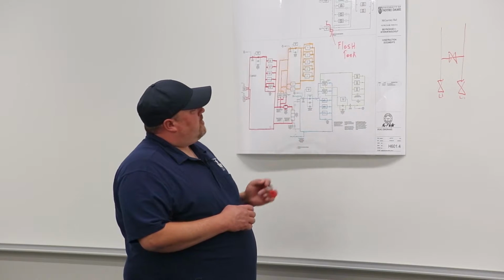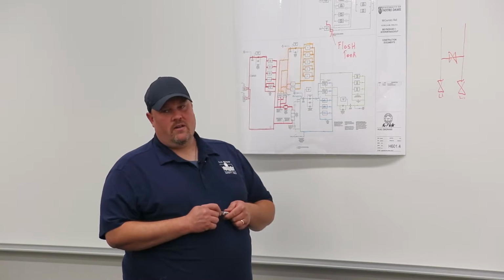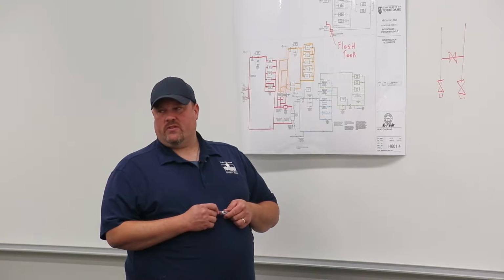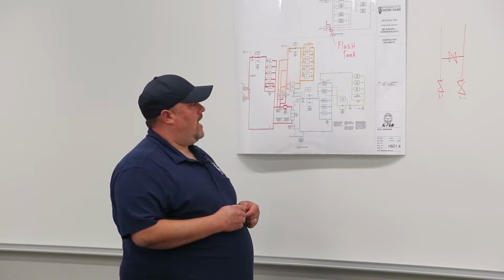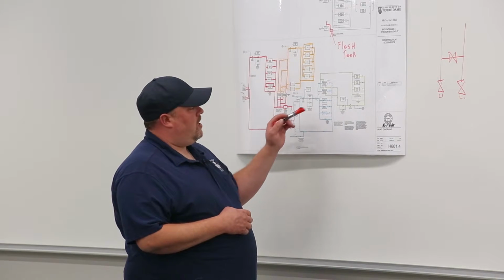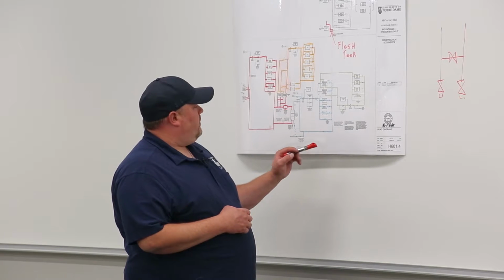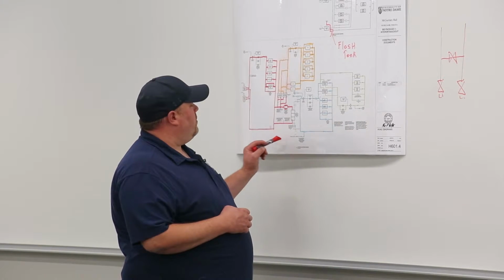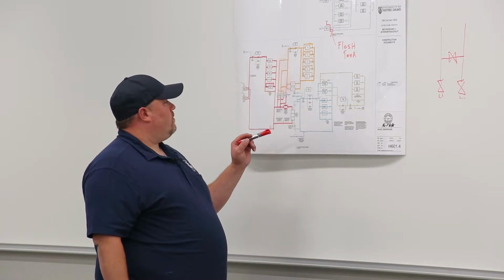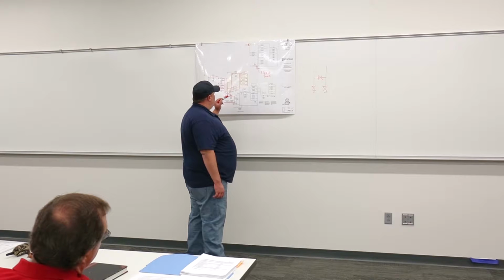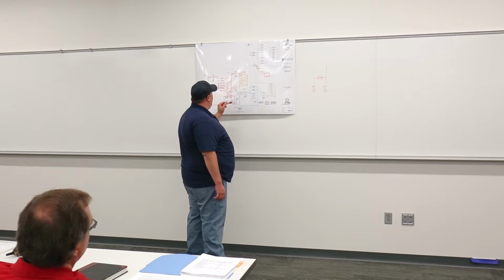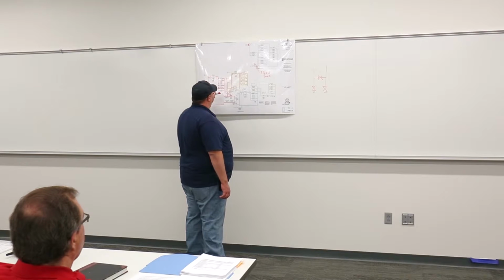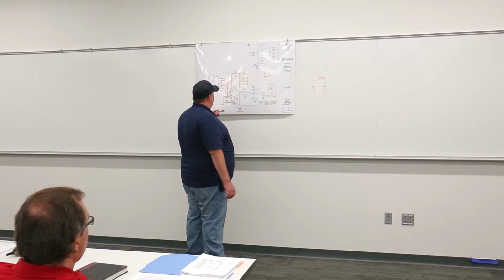We've got several fan coil units throughout the building that it runs through, and for the most part, they're for IT rooms and electrical rooms, is where most of those are located. Everything else for cooling inside the building all comes from the air handlers. The system loops back through and returns to plant. We also have our heat recovery chiller, which will turn on when the campus system is off and will actually cool this loop. But as that works, it rejects the heat instead of going to just the ambient temperatures of the air, and helps boost our heating system in the winter months. It supplements what it can to the system.